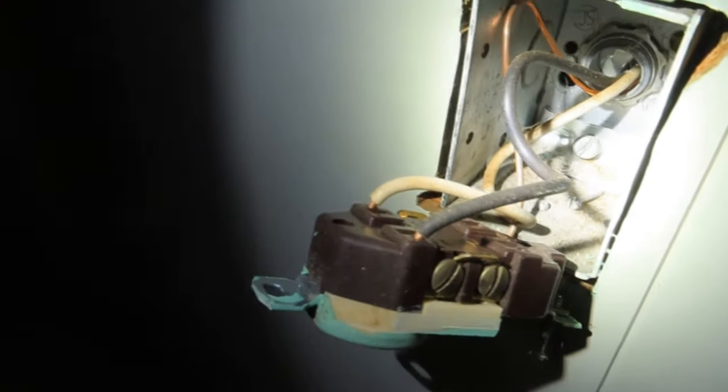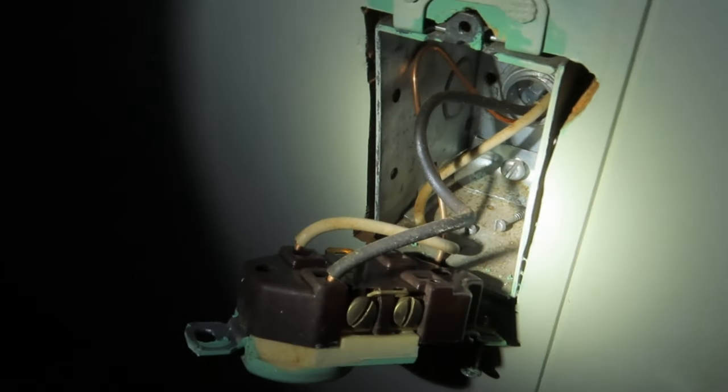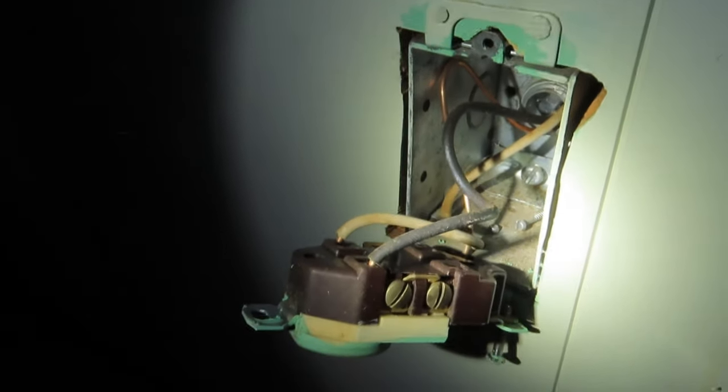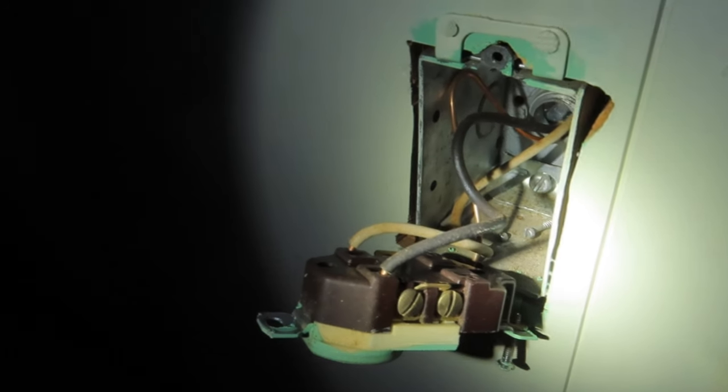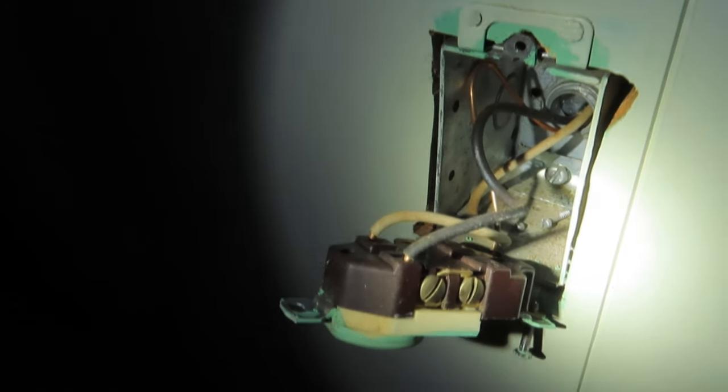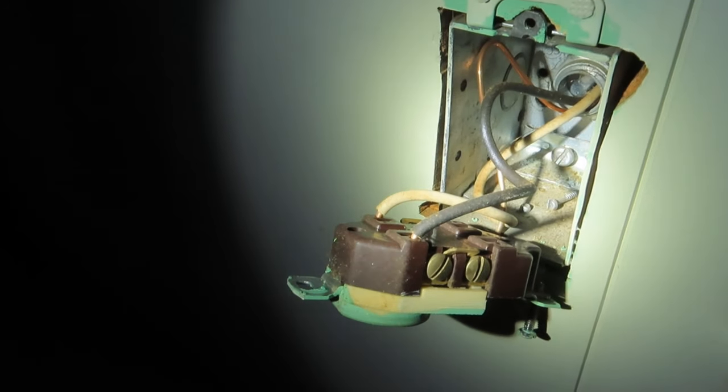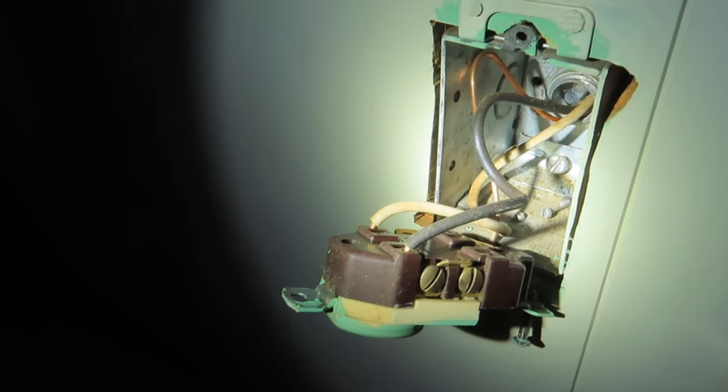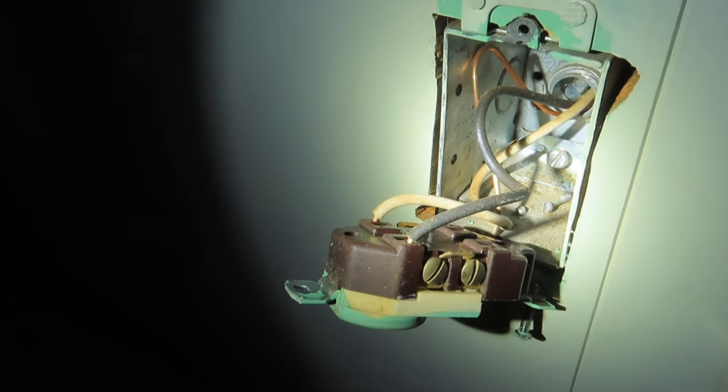At this place they do, I learned this term, it's called backstabbing, where you put the wires in the back like that instead of on the sides. The breaker's off by the way. This one was working no problems, but it's not really the right way to do it. It's kind of the rushed way to do it.